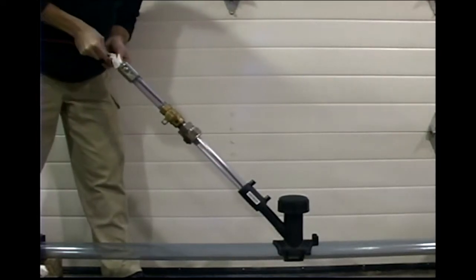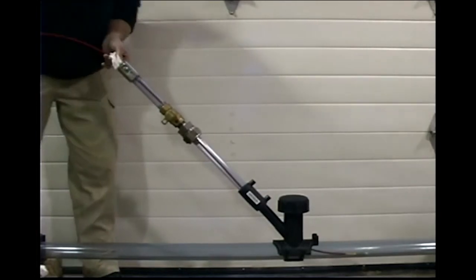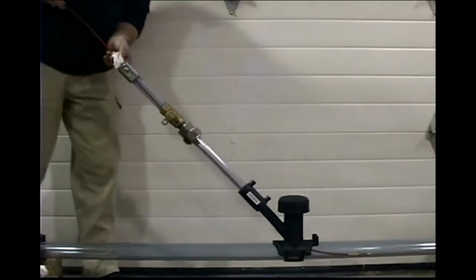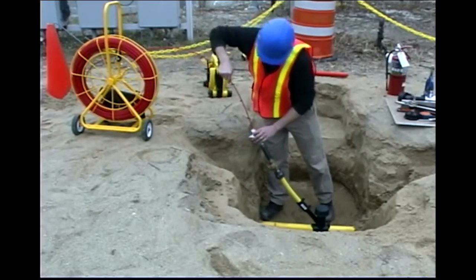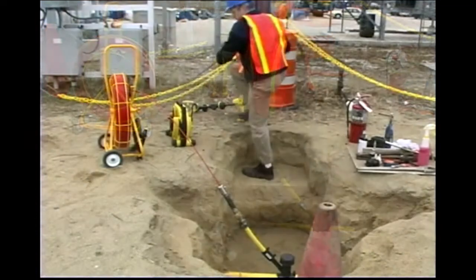When pushing the rod, keep hands within one foot of the stuffing box to avoid kinking the rod. Do not attempt to force the rod past an obstruction. Set the drag on the reel brake of the rodder so the reel turns slowly while pushing the rod. If the drag is too loose, this can cause the rod to unwind outside the cage.